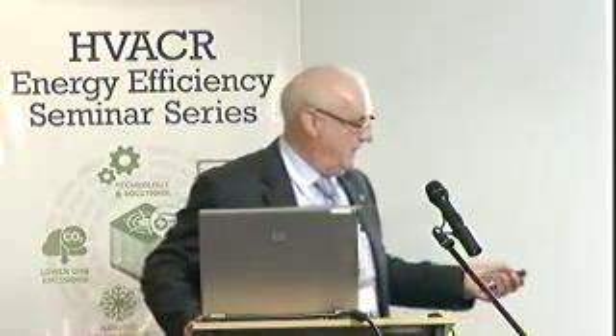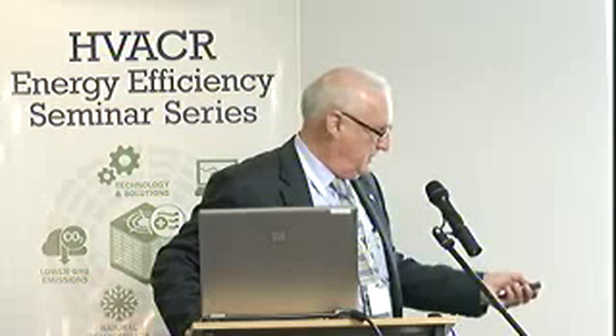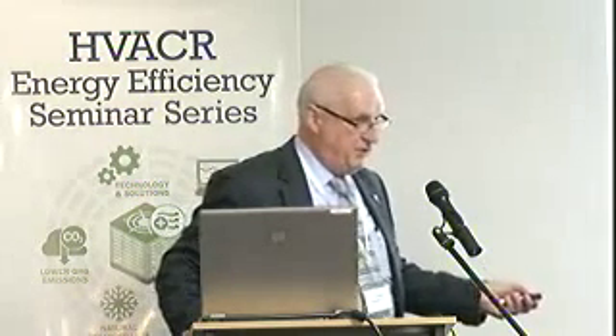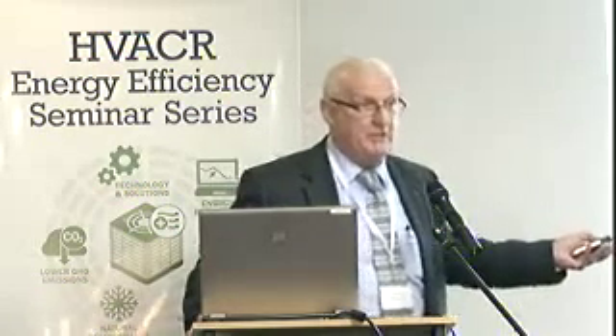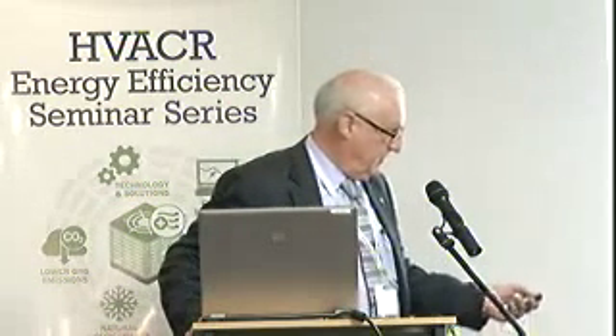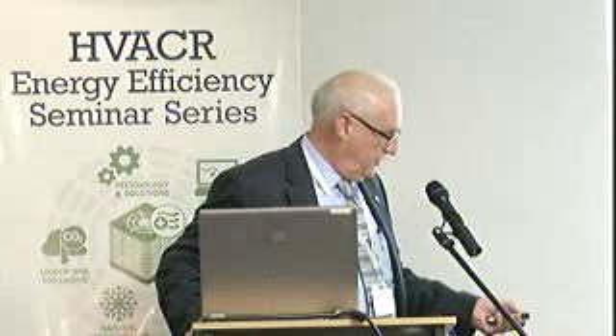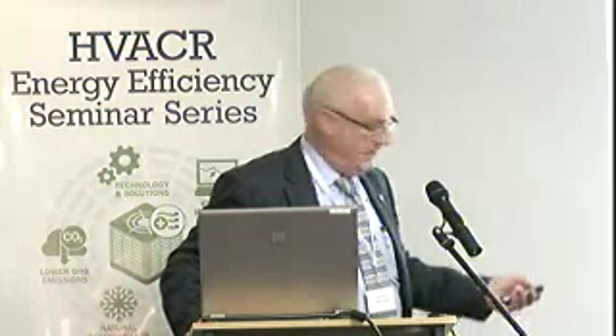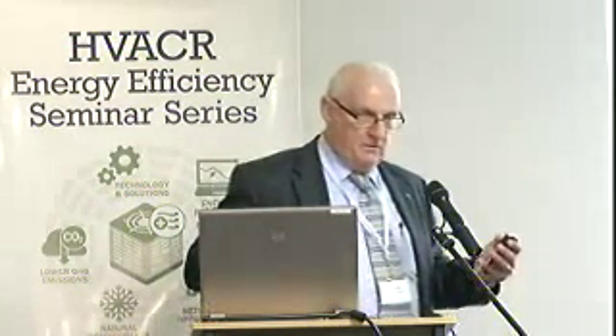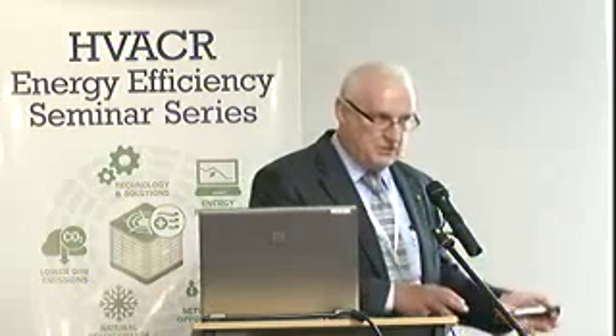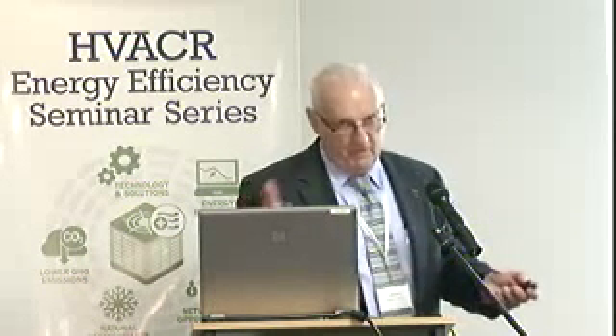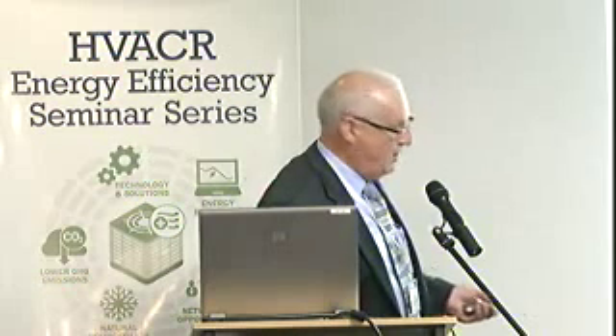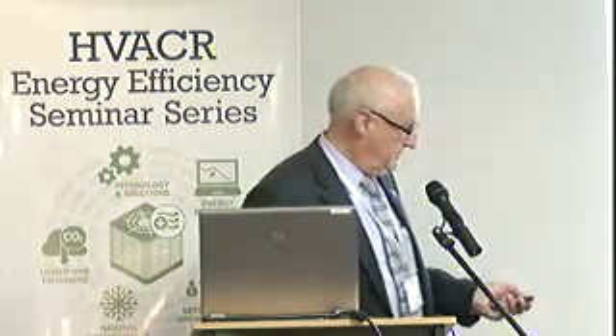This is just a quick example of the differences you can see. This is the supply voltage. This is if it were varied by 6% by a fixed tap voltage optimiser, which do exist and are a legitimate technology. And here's a stabiliser on that same input voltage. Now, these are models. Well, this one's actual. That's a model, reducing that by 6%. And the percentage voltage reduction is pretty close to linear to the percentage energy saving, depending upon the type of equipment, like we talked before. But down here, this ends up an average of about 9% energy saving versus 6%. So the average voltage is reduced by about 9%.